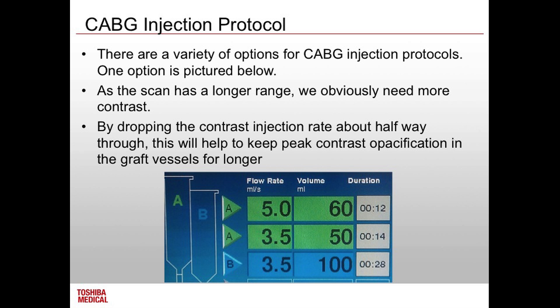What injector, did you guys get the Maxion injector? Yeah, good, so you know what that's going to look like. So it's a little bit different for a coronary artery bypass graft, and your application specialist will talk to you about the way you want to do this. So the trick with these ones is that you actually still want to keep your LIMA and your venous grafts opacified.